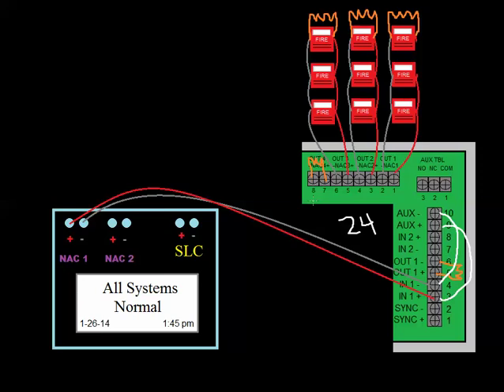The only thing to keep in mind if you do that is, usually you'd use that for maybe resettable power for smoke detectors or maybe power to door holders or something like that. The only thing to keep in mind is whatever your FCPS is rated for, you actually get 2 amps less current than that.